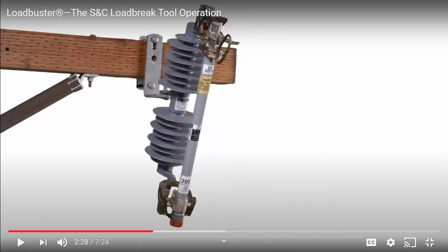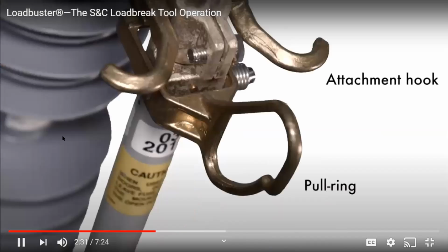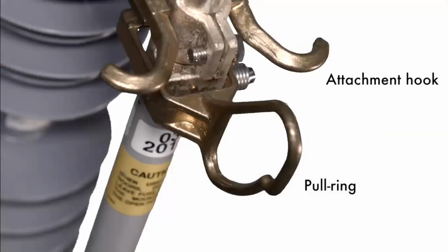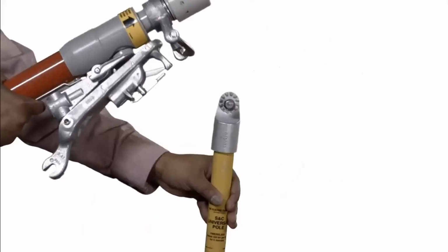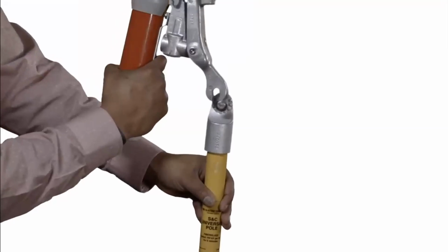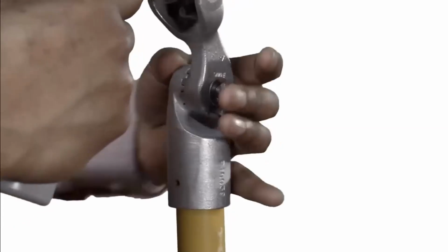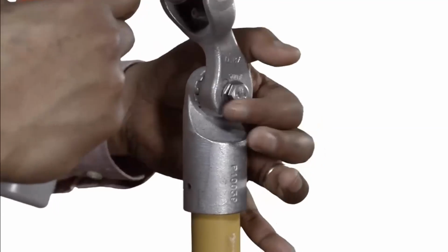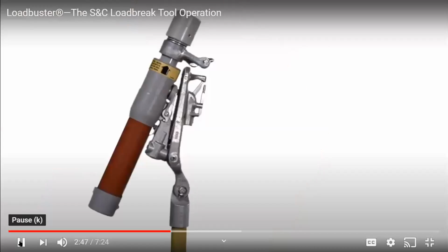Now this is not a normal one that you can replace in a fuse barrel. You'll notice this is completely different. This is actually a switchgear fuse. Disconnects, power fuses, and fuse limiters with an attachment hook at the upper end of the device and a pull ring on the device's switchblade or fuse tube. For usual operating conditions, the Loadbuster tool is fastened to a universal pole not less than 6 feet, 183 centimeters long, with the frame of the tool in line with the pole.